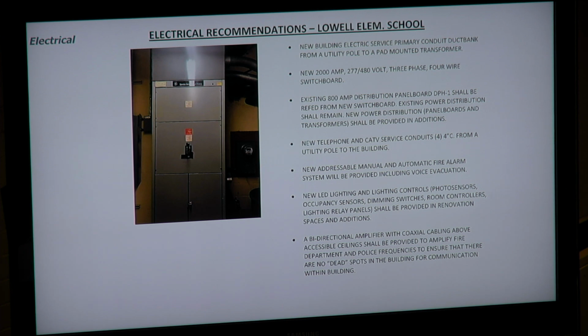Lowell School, it's exactly the same, except instead of a 1600 amp service, we'll be bringing in a 2000 amp service for Lowell, just because it's bigger. We'll be backfeeding the existing 800 amp panel. The switchgear that's in these schools, the 800 amp services, is in good shape, and it can be serviced and maintained. So instead of just tearing everything out, we can put in a new panel and backfeed what's being renovated.